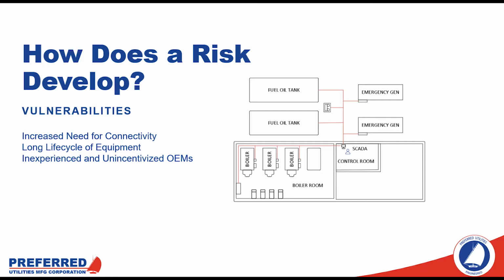If an attacker is able to access that network in some way, especially if you're using Modbus TCP, which requires no authentication or authorization to modify or read points, an attacker just by being on the network has the ability to modify the operations of your systems or even potentially disable them from operating as intended.